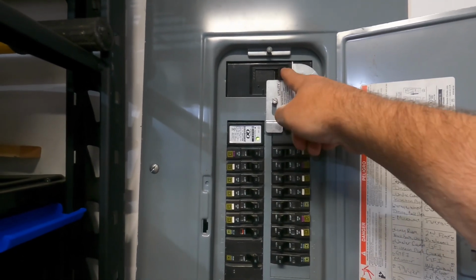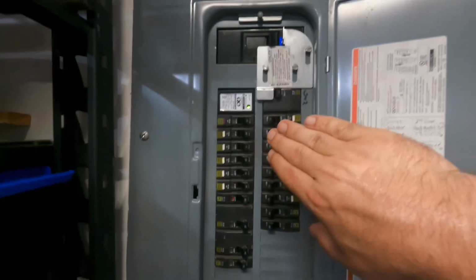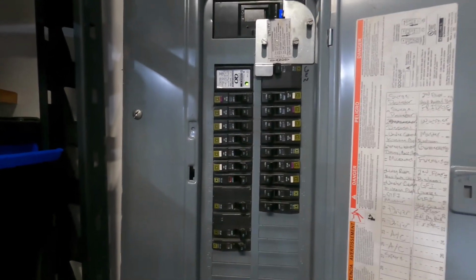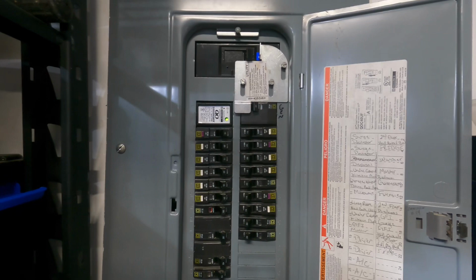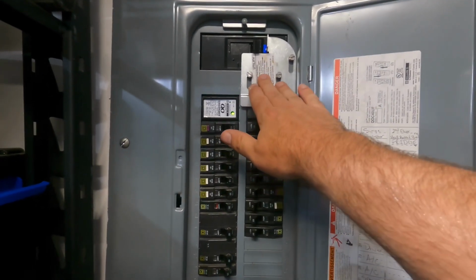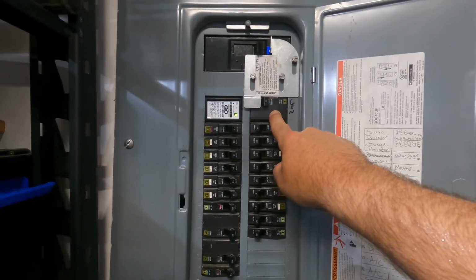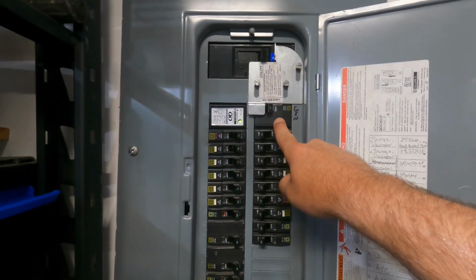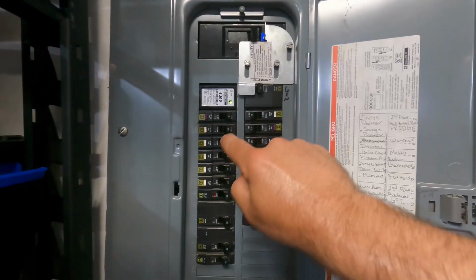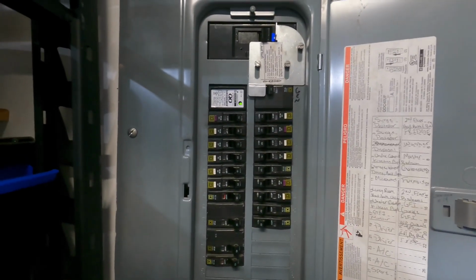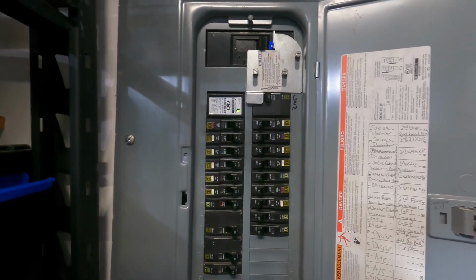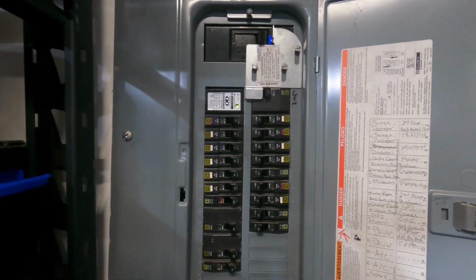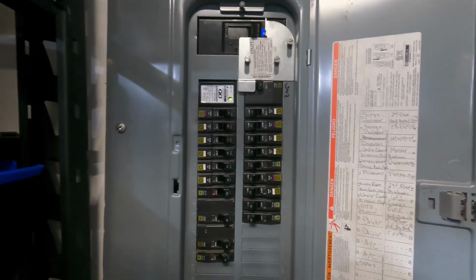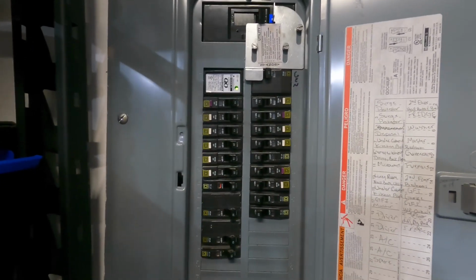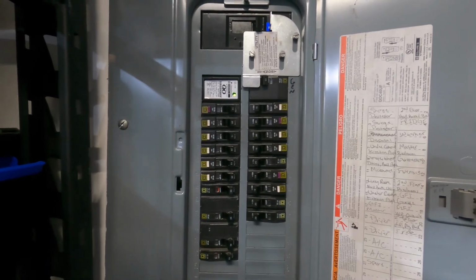Basically, when the power goes out, I'm going to have my main flipped off and turn off all of my different circuit breakers to all my different circuits. At that point I can press this up, which allows me to turn the generator breaker on, a 60 amp breaker, and then select the different circuits I'd like to run. This particular setup won't run my HVAC system, but it will run everything else, and also allows me to run a couple window units. So you're not going to get everything you had before, but you'll still be pretty well set up.